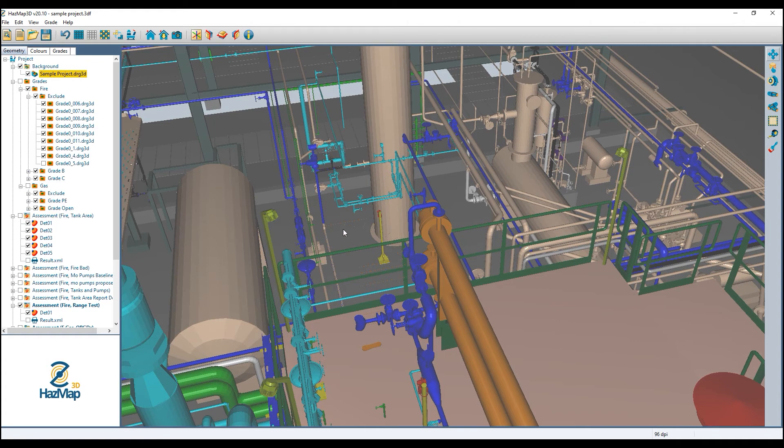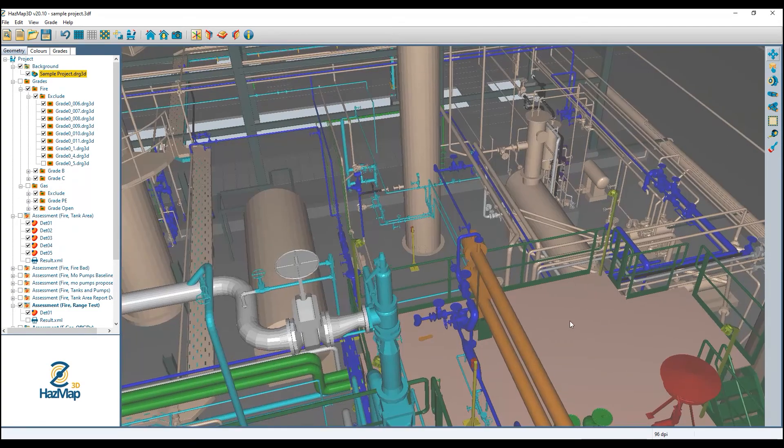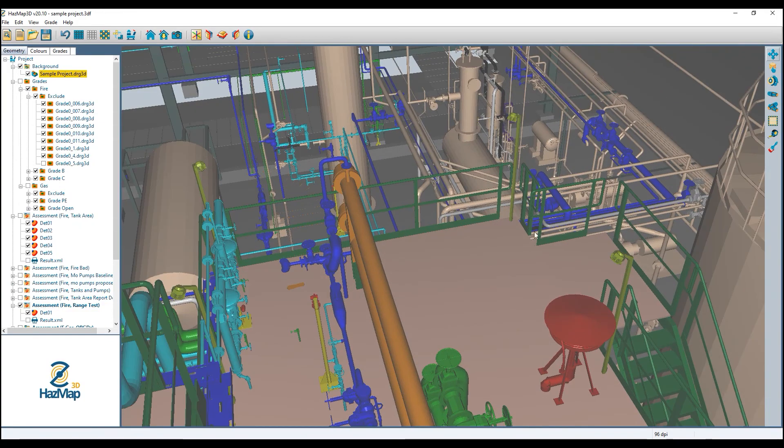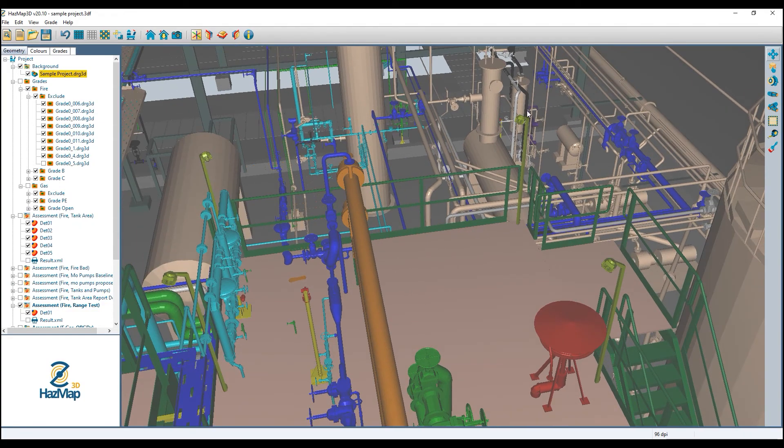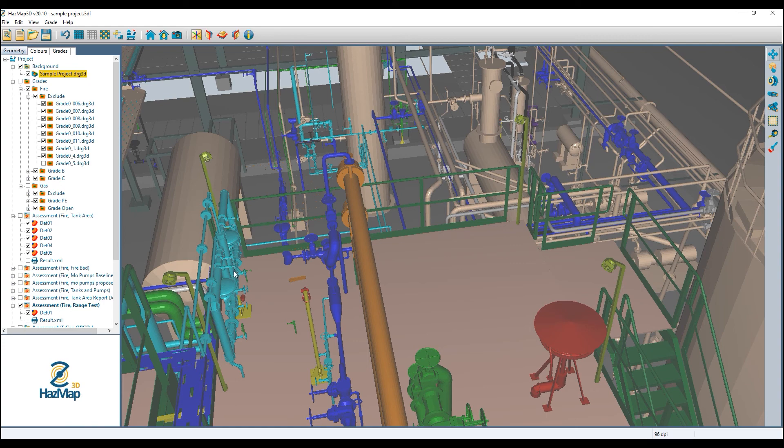If I put a flame detector here on this post and have it facing back into this area, that 3D worker would count as a 3D visual obstruction for the flame detector, and I would have a severe loss of coverage or much lower coverage assessed for this area. Same thing if I put a flame detector here and had it facing back over there—I wouldn't see much of this piping behind that 3D worker because the 3D worker would be blocking my field of view. That's why I delete him.